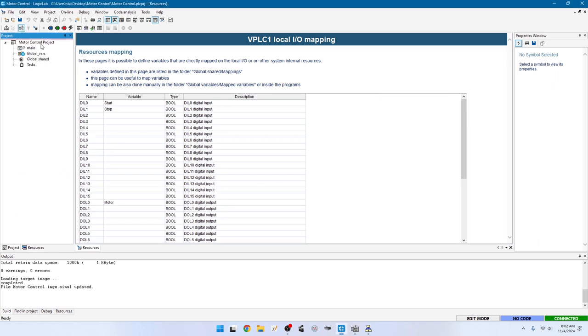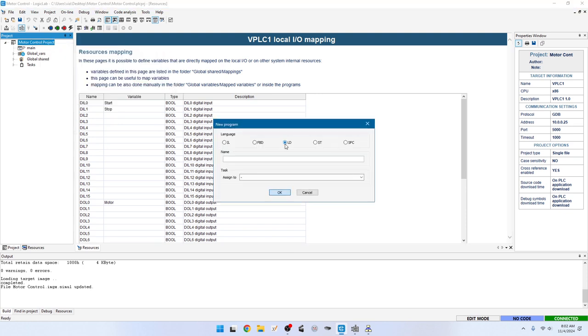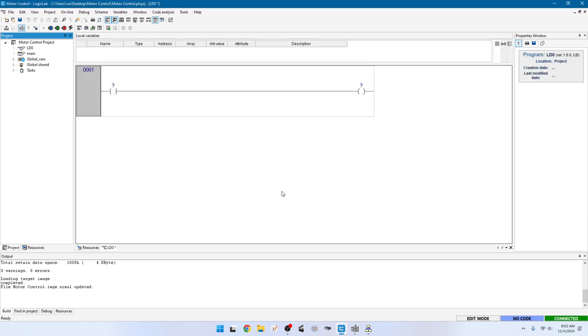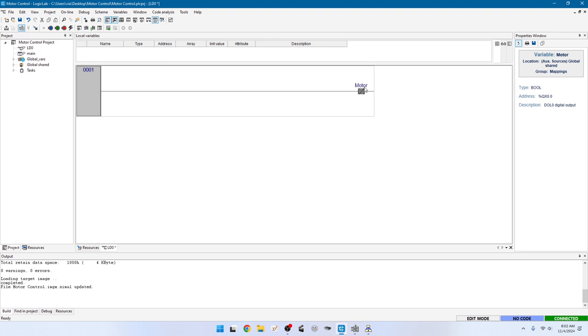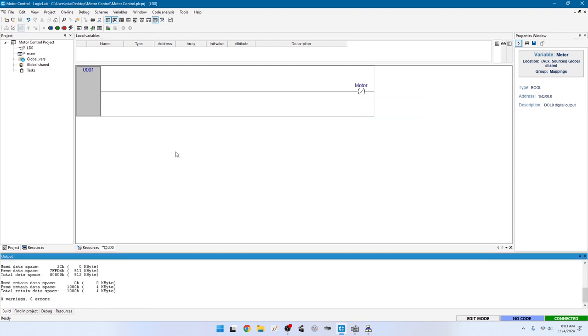Now go back to Project, right-click on Motor Control Project, and add a new program. We're going to make this a ladder diagram, then transition to function block diagram. Let's call this LD0 for the initialization program and assign it to the initial task. It gives you a skeleton with one contact and one coil. We don't need the contact — select it and hit delete — then double-click on the coil. We're going to set the motor variable initially to zero. Put in Motor and choose a negated coil. The slash symbol shows this is the NOT operation. So this is hardwired in and energized, but because it's a negated coil, that makes the motor variable become zero or false.